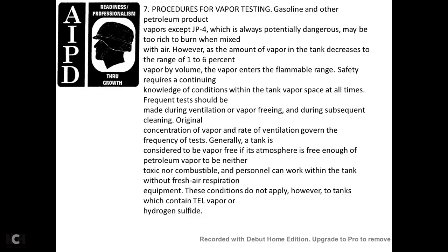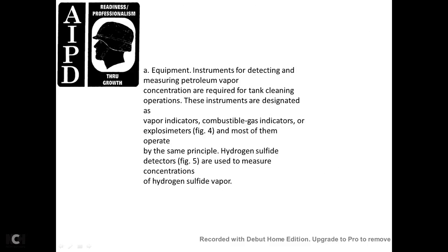Vapor testing: gasoline and other petroleum product vapors, except JP-4, may be too rich to burn when first encountered, but as they mix with air the vapor concentration decreases to the flammable range of 1 to 6 percent by volume. Frequent testing should be made during ventilation and vapor freeing and during subsequent cleaning to monitor vapor concentration. A tank is considered vapor-free when the atmosphere contains a non-toxic and non-combustible concentration of petroleum vapor, allowing personnel to work without fresh air respiratory equipment. However, this does not apply to tanks containing tetraethyl lead vapor or hydrogen sulfide. Instruments for detecting and measuring petroleum vapor concentration are required for tank cleaning operations, and are designated as combustible gas indicators or explosimeters.